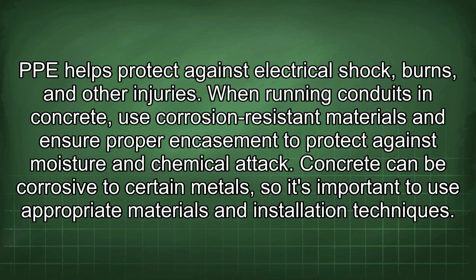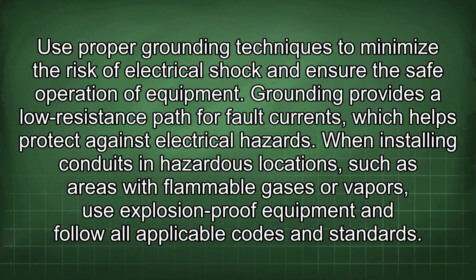When running conduits in concrete, use corrosion-resistant materials and ensure proper encasement to protect against moisture and chemical attack. Concrete can be corrosive to certain metals, so it's important to use appropriate materials and installation techniques. Use proper grounding techniques to minimize the risk of electrical shock and ensure the safe operation of equipment. Grounding provides a low resistance path for fault currents, which helps protect against electrical hazards.